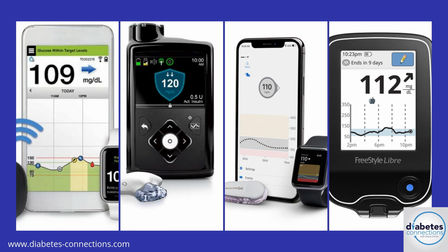The systems each have their share of pros and cons. I would say, from an accuracy standpoint, the implantable sensor probably has the best accuracy, but it has to be surgically implanted and calibrated a couple of times a day. But the Dexcom G6 is very close in terms of accuracy with no calibrations at all, followed by the Libre and the Medtronic. I'm still waiting for Medtronic to launch a really state-of-the-art effective sensor. Hopefully the next generation systems will prove better than the ones they've had in the past.